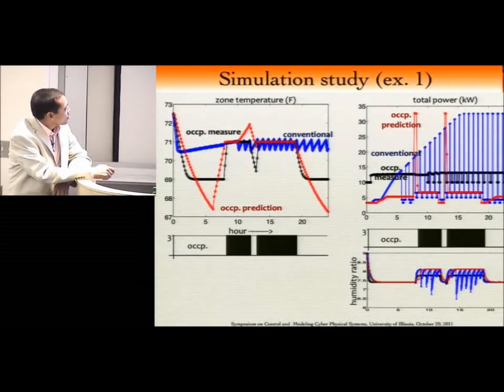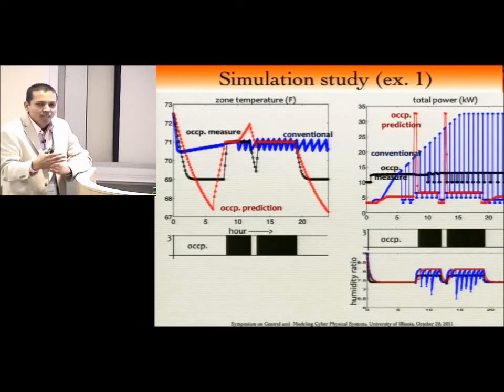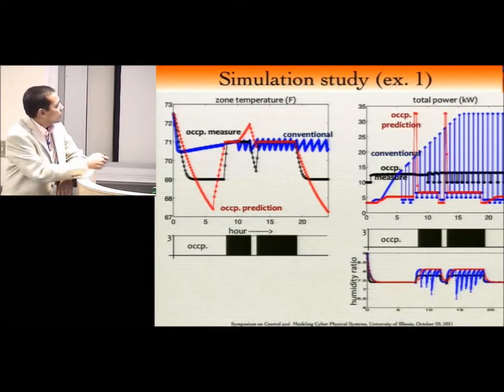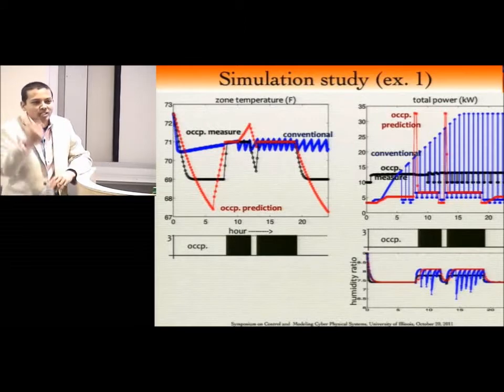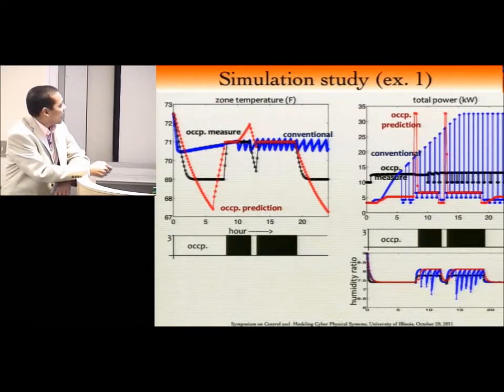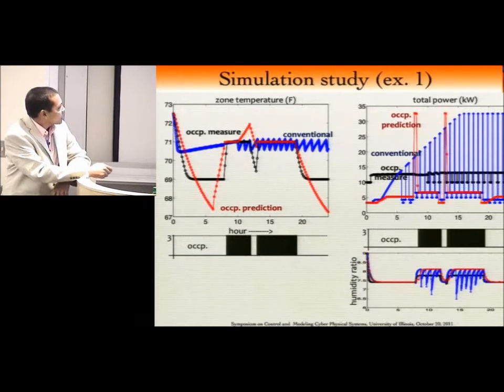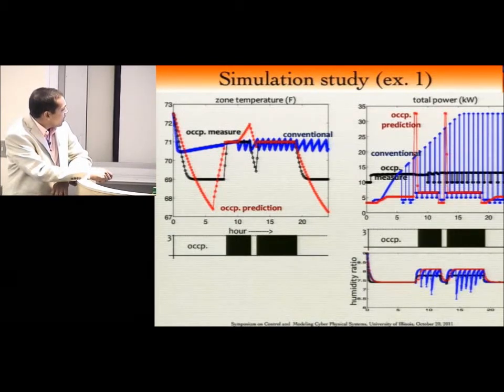Now what happens with the black one, which is the controller I just described, is that because it doesn't have such good long-term prediction, when it is in the unoccupied mode it does go down, but the design constraints are that you cannot go below 69, because I don't know when it's going to suddenly switch to an occupied mode, and I have to bring it up quickly. That's the only difference, and this is for this occupancy profile. Occupancy goes from 0 to 3 around mid-morning, then a lunchtime break, and then in the afternoon it is occupied again.